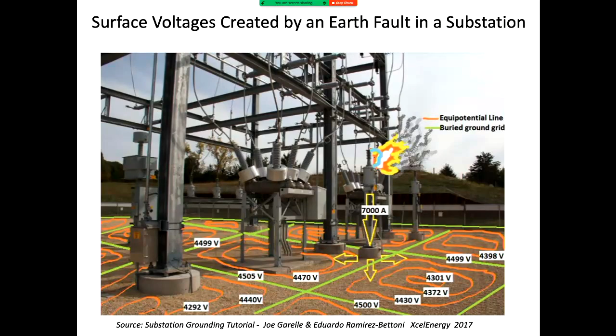You can see here someone's shown a fault in the substation going back out of it, and the voltages differ depending on where you are. So again, it's this issue: if you're touching something at 5,000 volts and something else at 4,000 volts, you'll get 1,000 volts between you. Touching something, or even walking across here, you can get a voltage difference. That's step voltage.